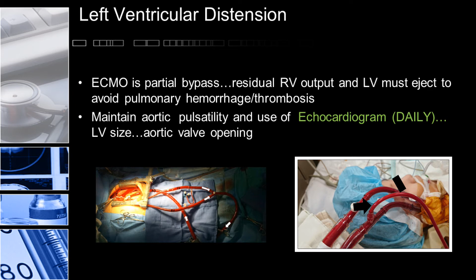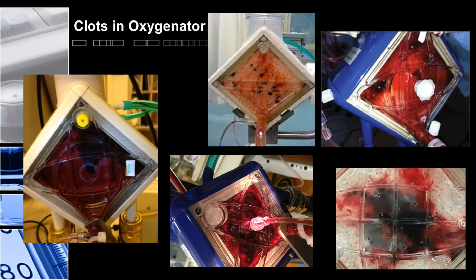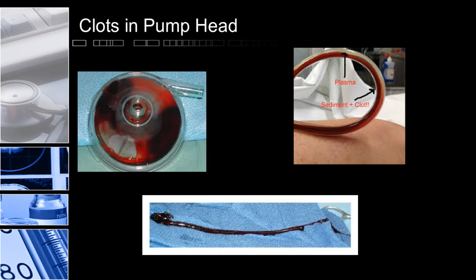If clots occur in the oxygenator, it can impair efficiency and ultimately will require that the oxygenator be switched out for a fresh unit. If a large clot occurs emergently, the ECMO specialist sitting the pump at the bedside must have the ability to replace the oxygenator emergently. In a similar fashion, clots can also occur in the pump head, impairing its efficiency or, in some cases, resulting in pump failure. Once again, the bedside ECMO specialist must have the ability to replace the pump head in an emergent situation.